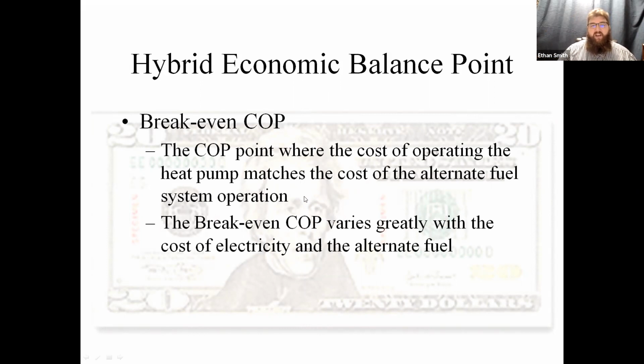For my customers that we were operating on an economic balance point, what my company would do is sit down at the beginning of the year and figure out what our utility rates were for all our various customers, whether they were on propane or natural gas. We just had a chart for what those were, and then we'd put down some COPs for the typical systems that we had. We always had the option to look up something if we needed to modify those break-even balance points, because it changed year to year.